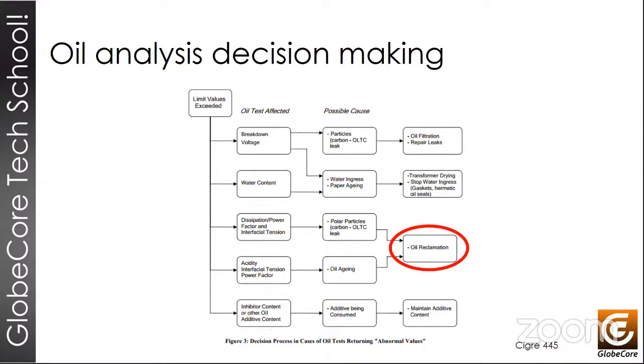Okay, so now we've seen the drying and vacuuming part, but we want to talk now about oil regeneration. If we have a problem with power factor or interfacial tension, if we have polar compounds in the oil because the oil has aged, if we have acids in the oil, which are extremely corrosive to the transformer and the paper, all of these indicate that oil must be regenerated. And this process is much slower and deeper than the thermal vacuum process. Next, please.